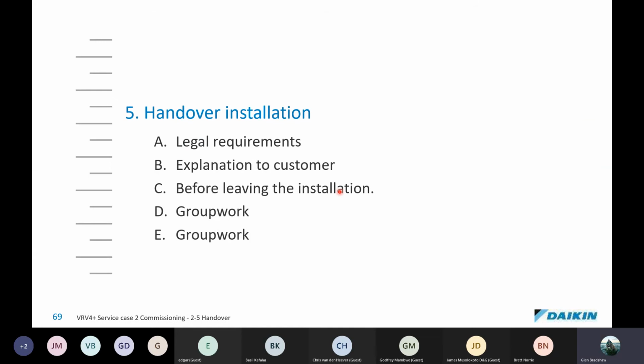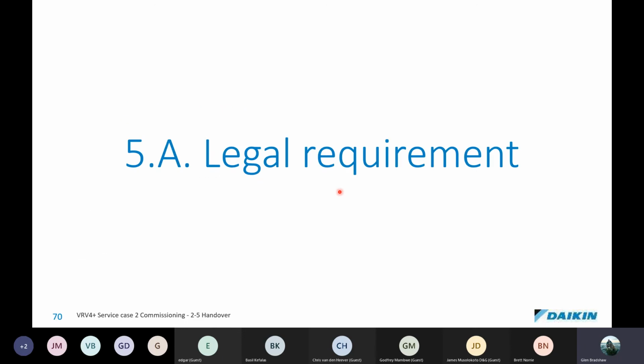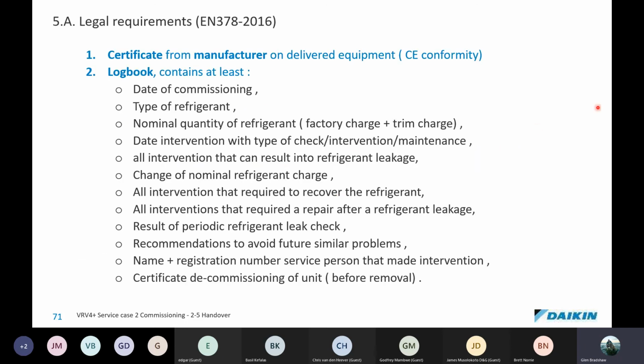Handover of the installation. If there are legal requirements, then these must also be met. So what are legal requirements? I can issue a commissioning form. At the end of an installation, that commissioning sheet indicates whether commissioning was successful or not, and if there are any items that need to be attended to. And sometimes we'll say that once the items are attended to, then we will pass the commissioning as passed.